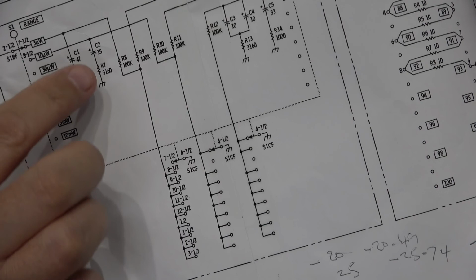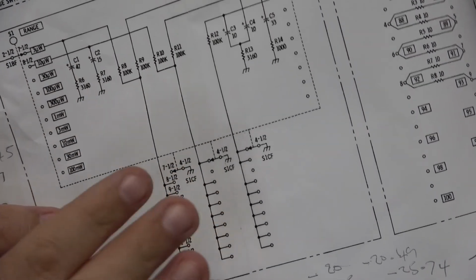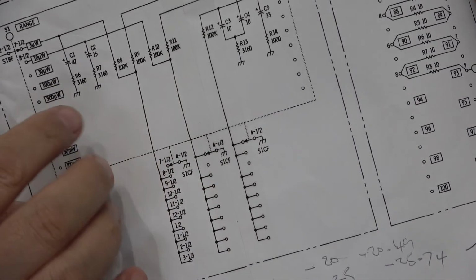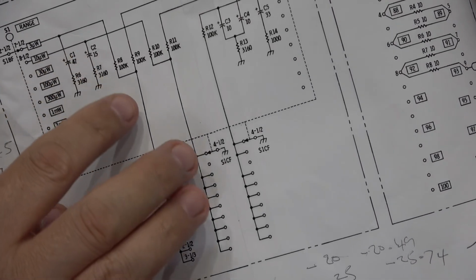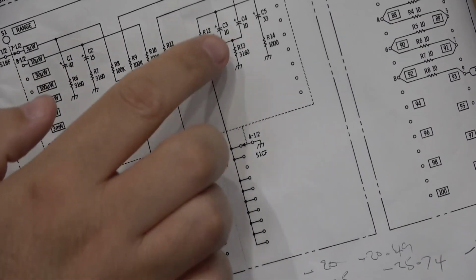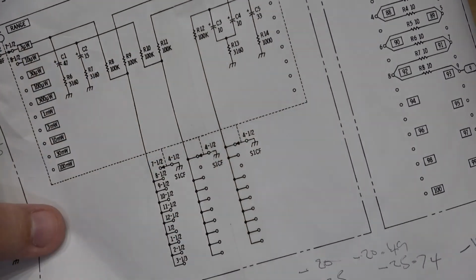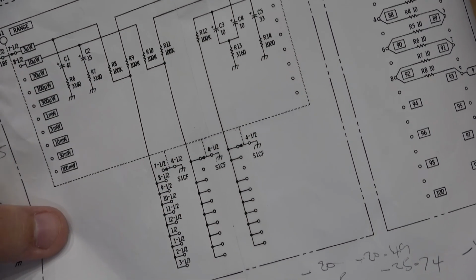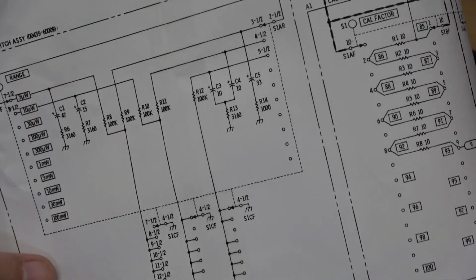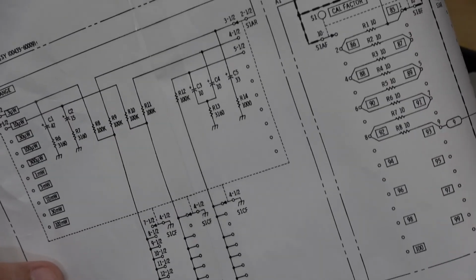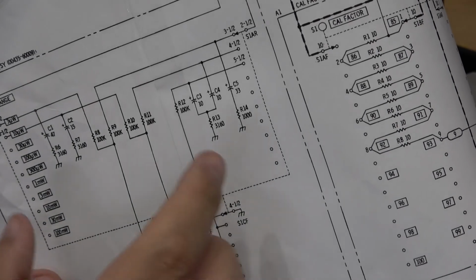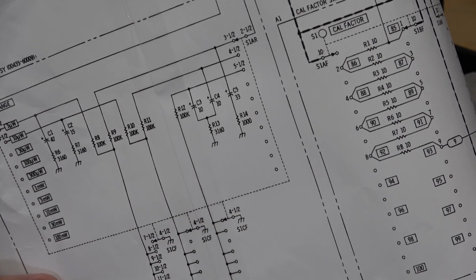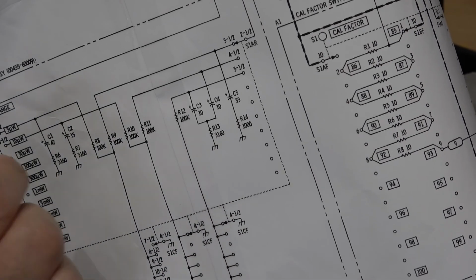Taking a quick look at the diagram, this is the section of the range switch just before the DC amplifier. So we can see several capacitors in series with resistors, and they're all going down to ground. So I've taken off capacitor 2, which is 15 microfarad, and I've tested it, and it is passing DC current. So essentially, I think that's happening on all of the ranges, and what's happening is it's just pulling the value down towards ground.